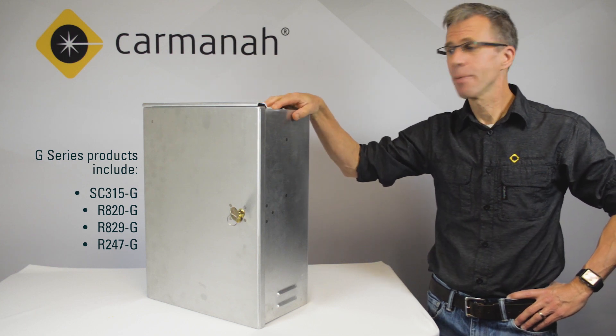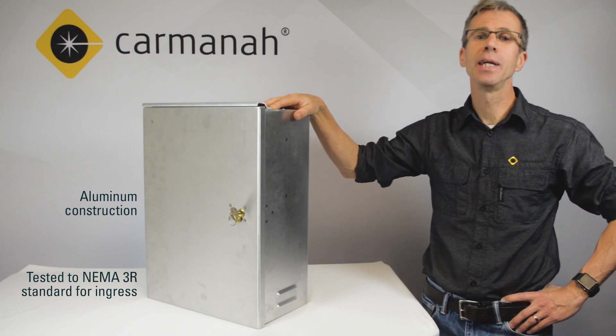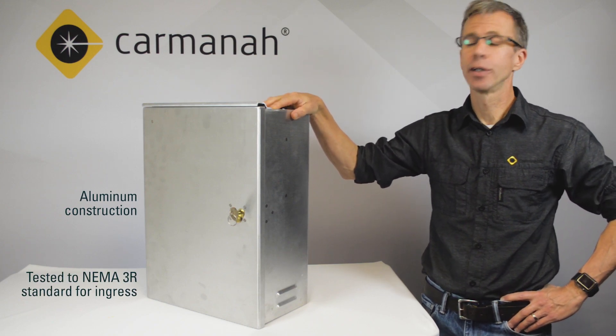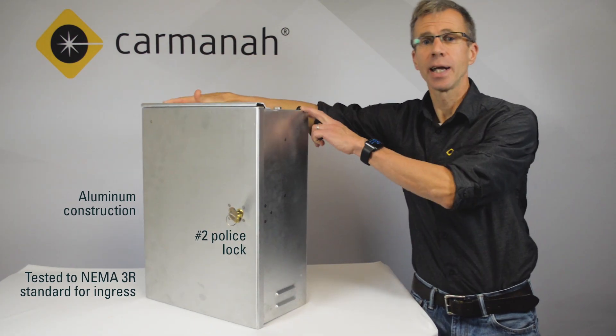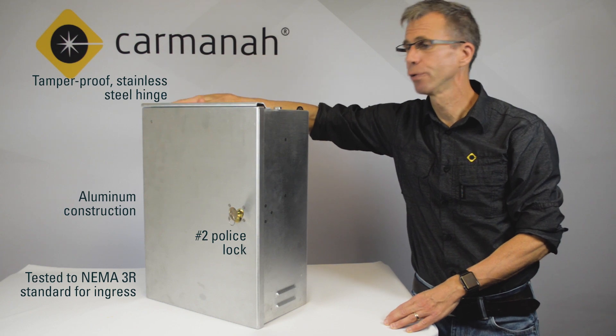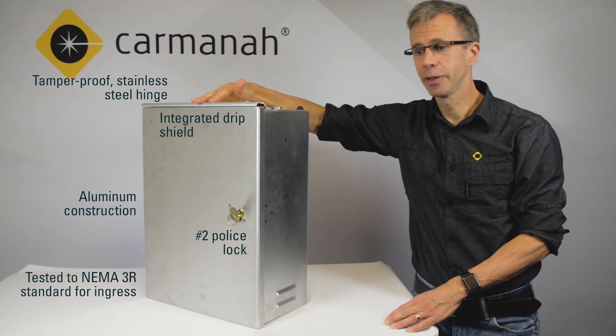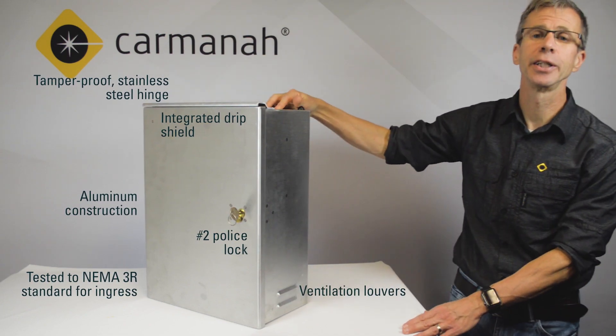First of all, the cabinet is made from aluminum. Carmanah designs and tests all of its traffic products to a NEMA 3R standard for ingress. The cabinet has a number two police lock. On the far side here we've got a continuous stainless steel hinge that's tamper proof, we have an integrated drip shield, and on the left and right sides of the cabinet lower down here we've got louvers for ventilation.